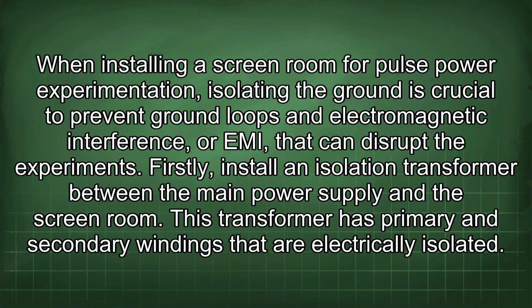When installing a screen room for pulse power experimentation, isolating the ground is crucial to prevent ground loops and electromagnetic interference (EMI) that can disrupt the experiments. Firstly, install an isolation transformer between the main power supply and the screen room. This transformer has primary and secondary windings that are electrically isolated.